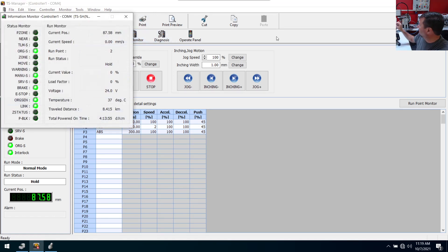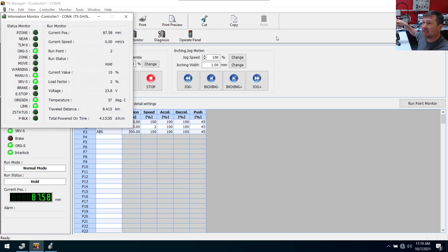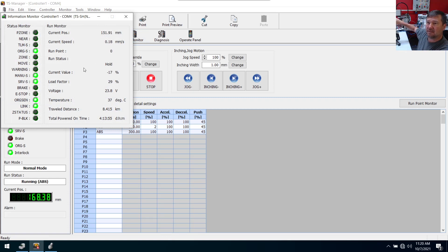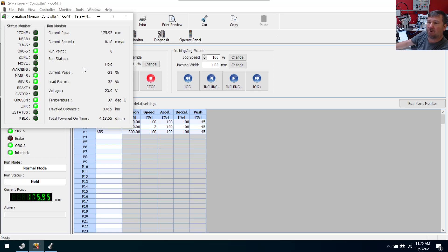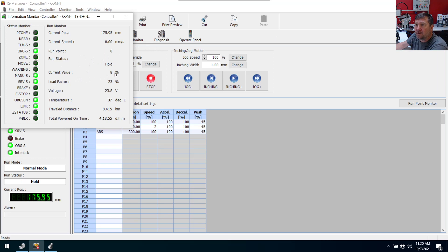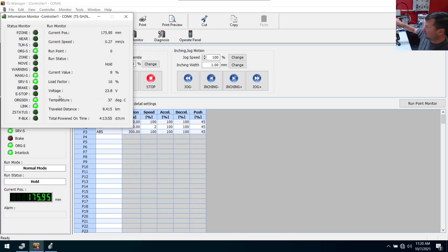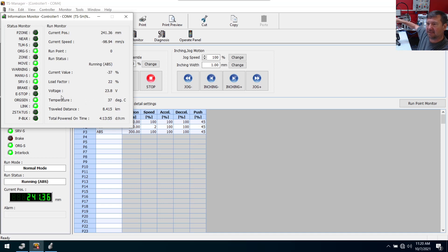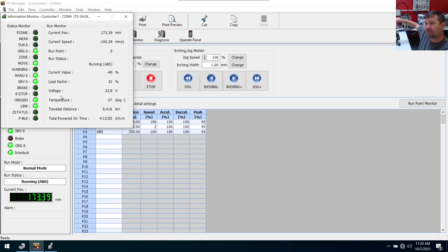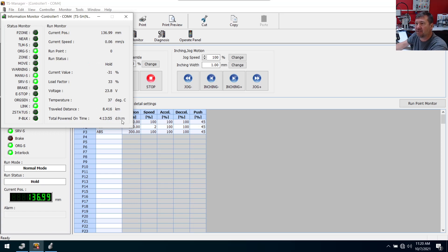Okay, this tells us the exact current position. So if I jog just a little bit, yeah, we can see our speed. And if we were running to a point right now, it would tell us which point. See current value. So then we have our load factor, gives us a temperature, distance traveled. Oh yeah, there you go. You got an odometer there. And we know the total time that it's been on.